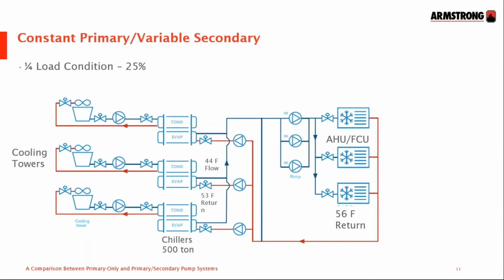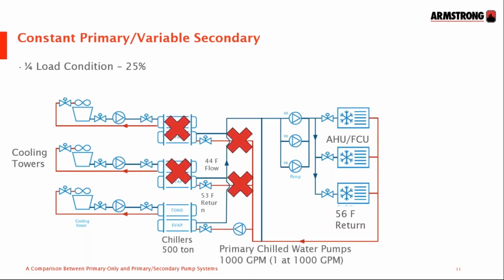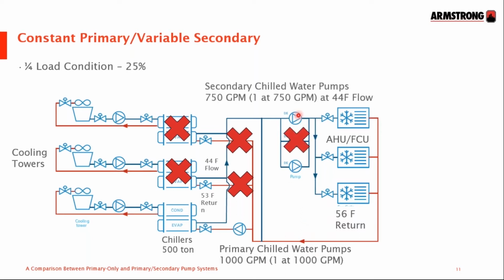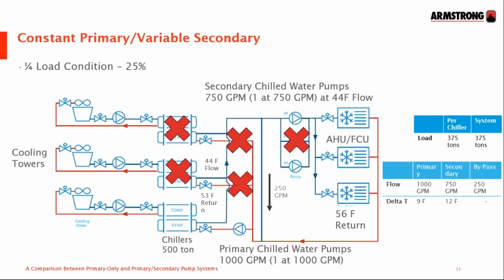At a 1/4 load, still using load-based sequence, we now turn off 2 chillers. We now have 1 1000 GPM primary pump, cooling that water from 53 to 44. In the secondary loop, the secondary pump slows to 25% of flow, or 750 gallons a minute on 1 of the pumps through that zone here, 56 in, 44 out. We have 750 in the secondary, 1000 in the primary, so you've guessed it, we have 250 in the bypass, mixing with the 750 coming back to produce this mixed 53-degree return temperature, a 9-degree delta T, and once again the chillers operating off best efficiency at 75. The 1 chiller working at 75% loading.